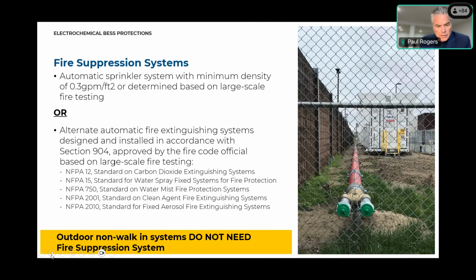You can also see there could be other alternative systems out there for fire suppression. Here's what I would tell you. Take a look at what they're used for. Make sure that if they're telling you they're using a different type of system for suppression, that it actually works. Ask for the data, ask for the testing that has been done with it. In some chemistries, the clean agents may work, or a fixed aerosol may work.